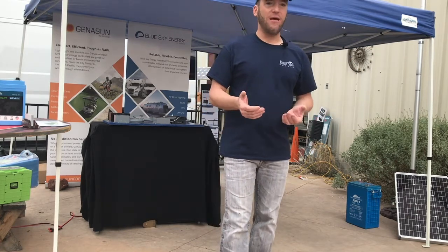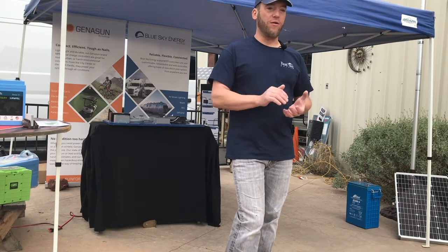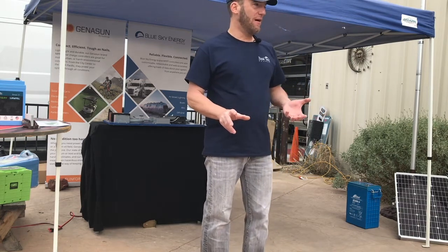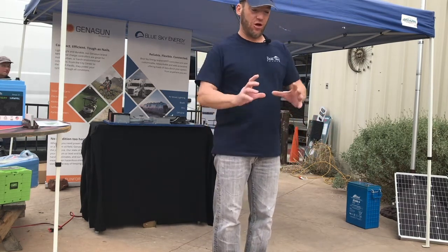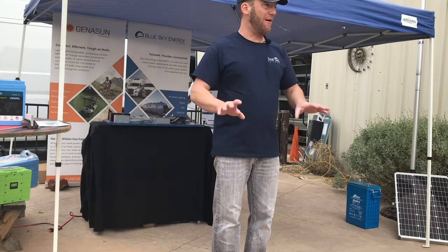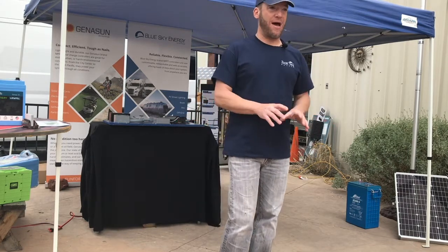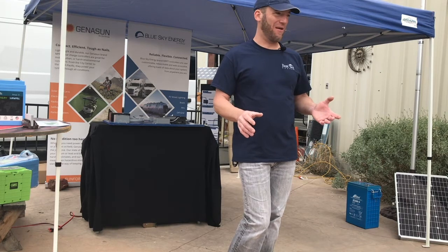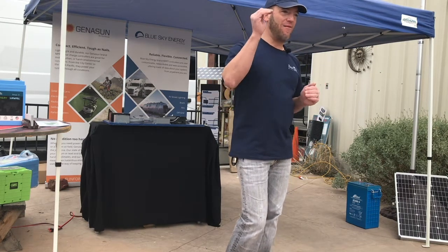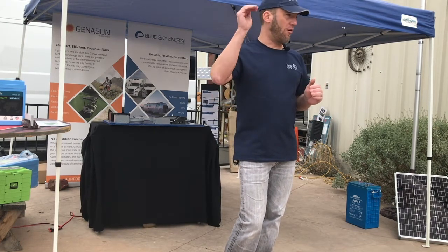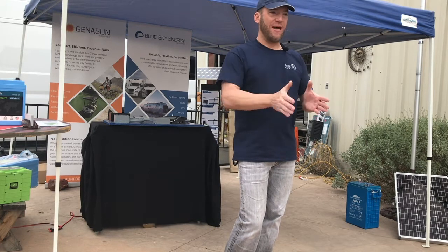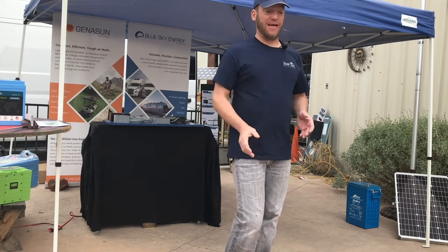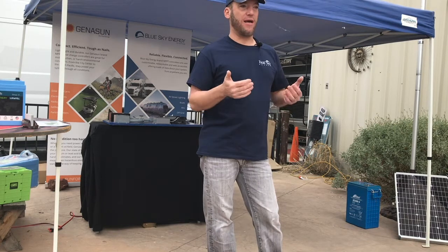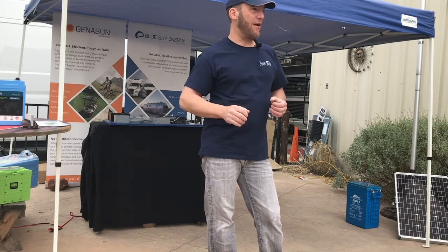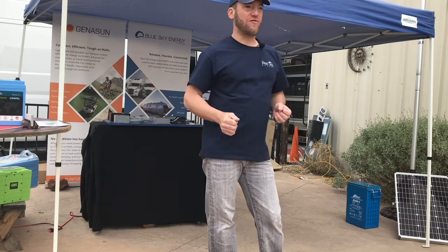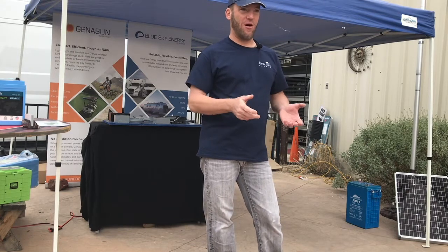It used to be thought that holding the float voltage — let's say 13.3 volts — indefinitely, like if you put your van away with just a little charger holding that voltage, meant your battery would be perfect when you came back. Not necessarily. You do want to get it every now and then to that 14.4, the absorption voltage, to make sure those plates stay clean. You don't have to get there every day, but you do want to get there on occasion. So when they say exercise your batteries, they really mean trick your charge controller to get back up to the absorption phase on occasion.